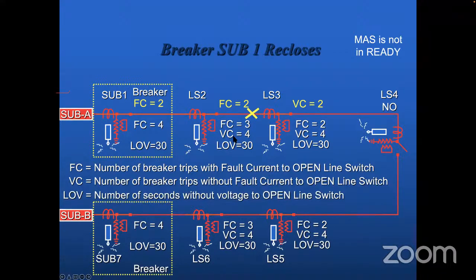Now again it will open up, and now your fault count becomes 3 here, fault count becomes 3 here, and VC count becomes 3 here. So this agent is programmed that when fault count equals 3, what is it going to do? This agent is going to open its own switch. Remember, if this switch is closed and it's seeing the fault current, this switch cannot be opened.